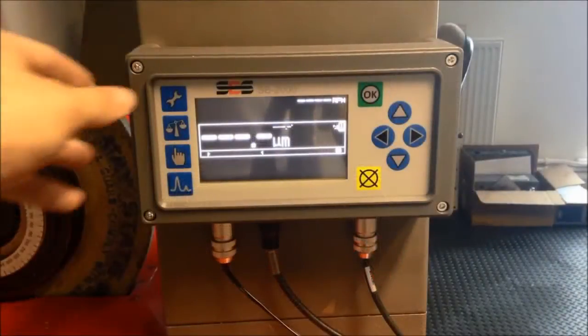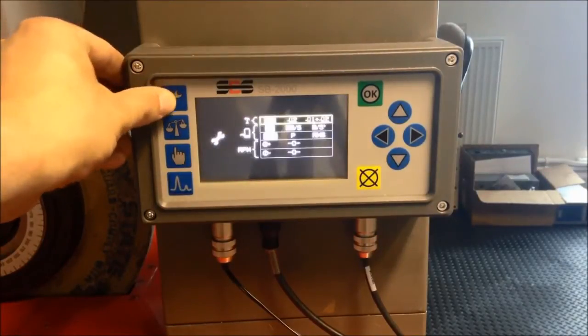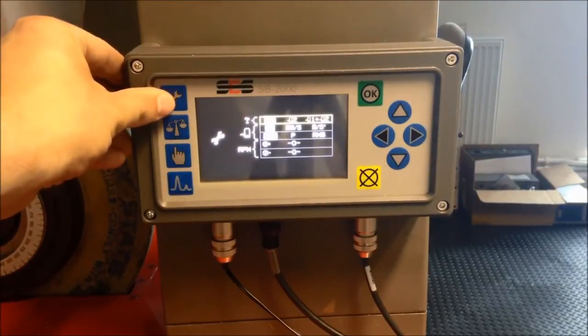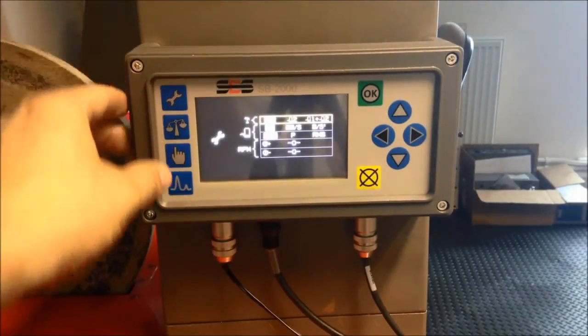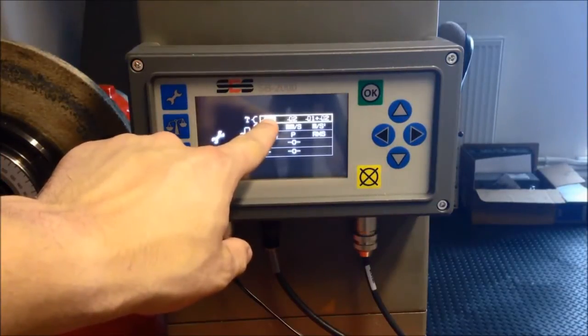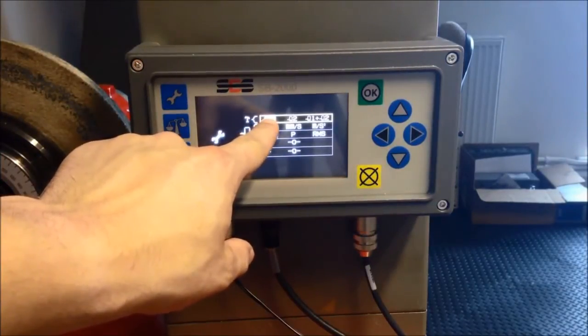Pressing the wrench button once makes the general settings. Here we select vibration sensor 1 for a single-plane balance. Vibration units in microns, peak to peak.